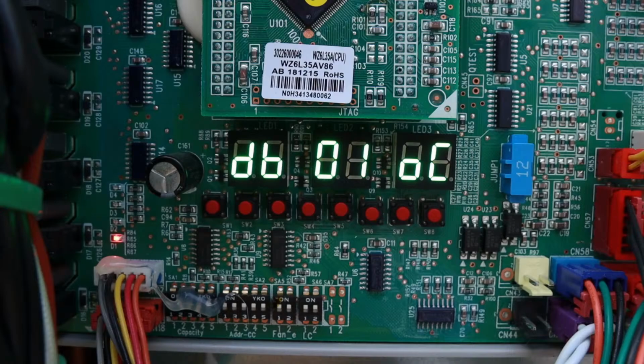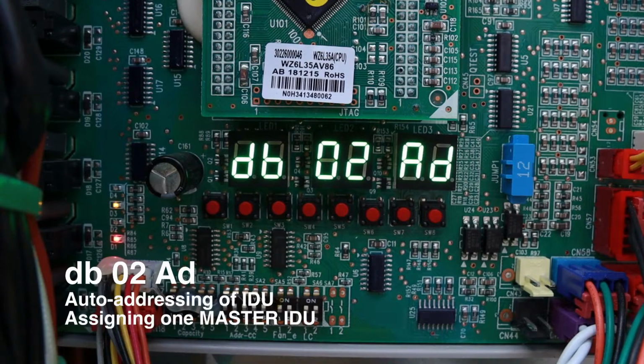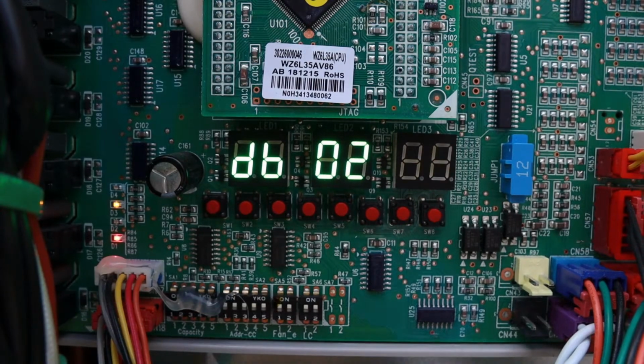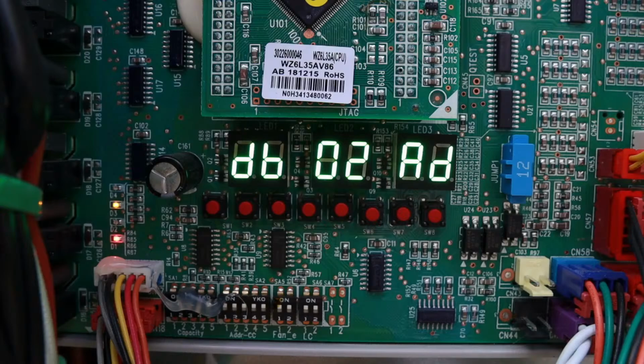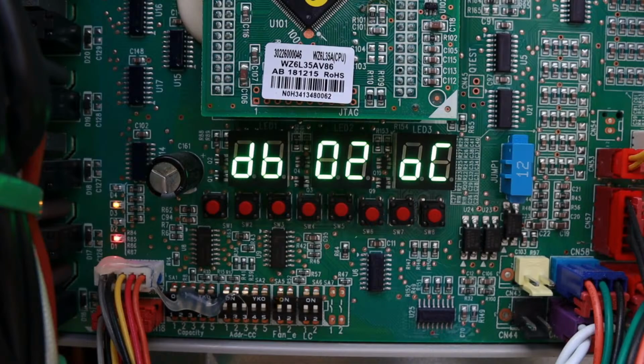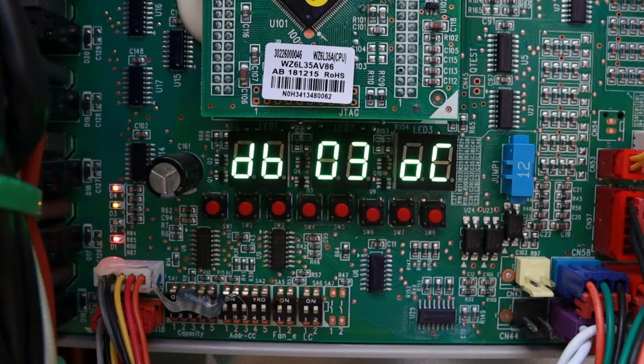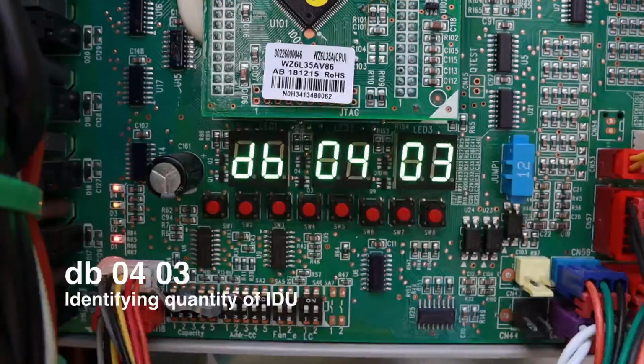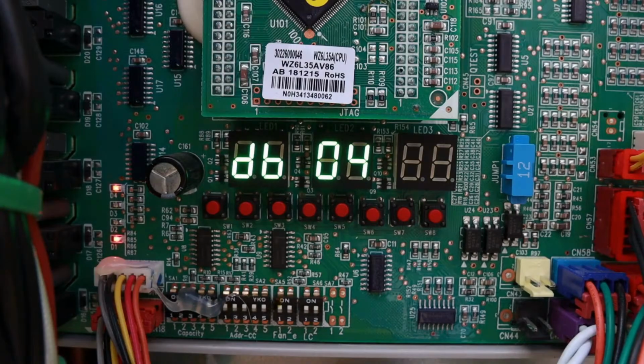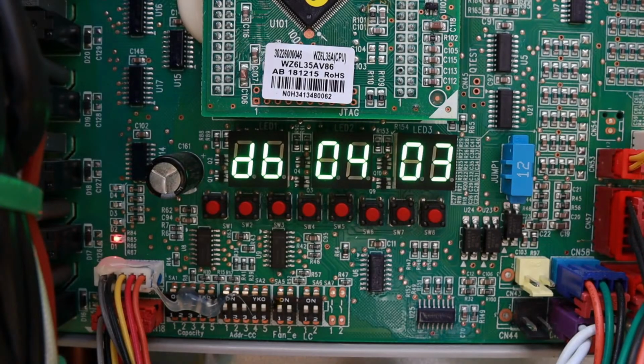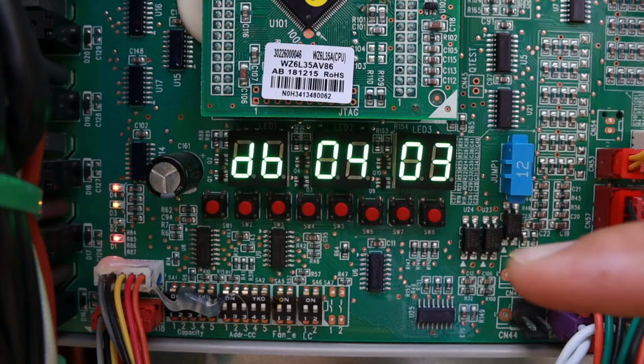Step 1 is checking for a master outdoor unit. Step 2 is auto-addressing IDs for the evaporators. It's automatic, it will take about a minute or so, and it will also assign a master indoor unit for operation of the whole system. Step 3 is identifying the quantity of condensing units. In this case, because it's just one, it will automatically jump to the next step. Step 4 is asking to confirm the quantity of evaporators. As I showed you before, I have 3 units in my house, so 3 is correct. So what I do is press SW7 to confirm the quantity of evaporators, and I just give it a second until it accepts the command.